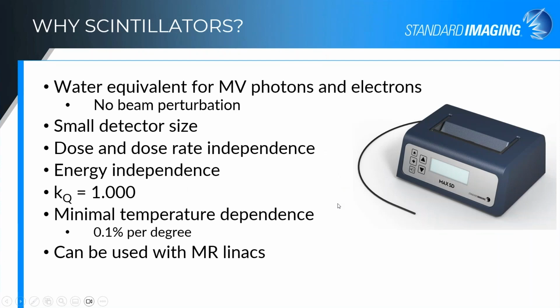So why scintillators in the first place? The reason for looking into scintillators rather than the standard ion chamber, diode, diamond type detectors is that they really are water equivalent for those megavoltage photons and electrons, which means for small field dosimetry, it's a huge advantage not to be perturbing the dose distribution right there at the point where you're trying to measure it.